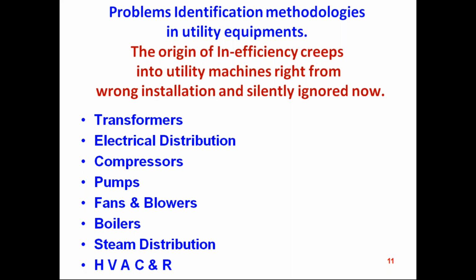For variable torque loads, especially centrifugal compressors, centrifugal blowers and centrifugal pumps, any amount of reduction in RPM will give a lot of energy savings. It applies to the fans and blowers also. Whether we have selected the right type, each and every discussion will be there in the next few sessions, where you will find what efficiency can be achieved on the pumps and on the blowers.